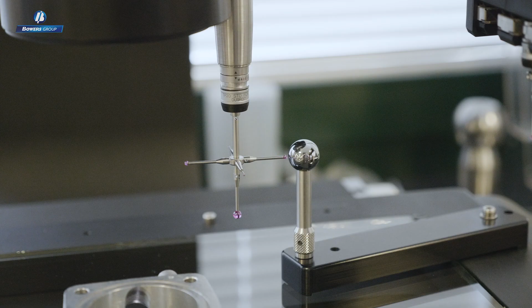The system obviously knows where the reference ball position is, and using that information we can not only calibrate and calculate the stylus tip diameter very accurately, we can also calibrate and calculate the tip position relative to the other tips and the camera. So having done this process now, I can select any of the tools in my probe library, and any dimensions that I make with any of those tools can all be related to each other because the offsets are known.